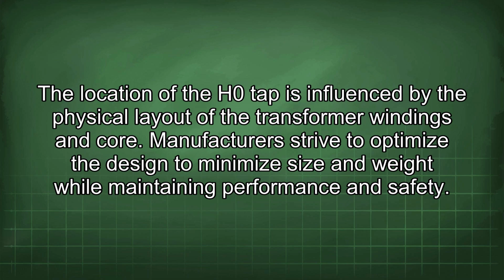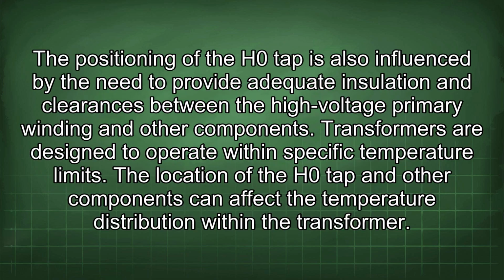The location of the H0 tap is influenced by the physical layout of the transformer windings and core. Manufacturers strive to optimize the design to minimize size and weight while maintaining performance and safety. The positioning of the H0 tap is also influenced by the need to provide adequate insulation and clearances between the high voltage primary winding and other components.